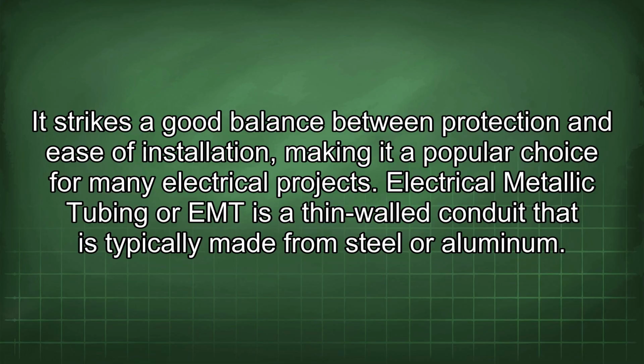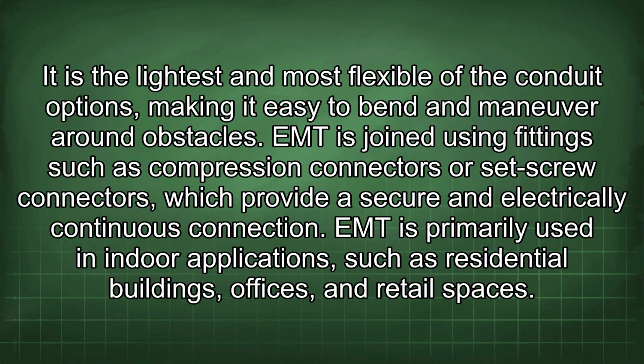Electrical metallic tubing, or EMT, is a thin-walled conduit that is typically made from steel or aluminum. It is the lightest and most flexible of the conduit options, making it easy to bend and maneuver around obstacles. EMT is joined using fittings such as compression connectors or set screw connectors, which provide a secure and electrically continuous connection. EMT is primarily used in indoor applications, such as residential buildings, offices, and retail spaces.